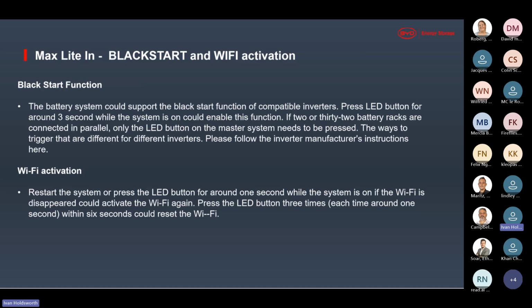There's also a black start function on the batteries, so you can power the batteries without communications active first. The way the batteries normally operate on a normal turn on is that the batteries will wait for communications to the inverter before they give output on their terminals.